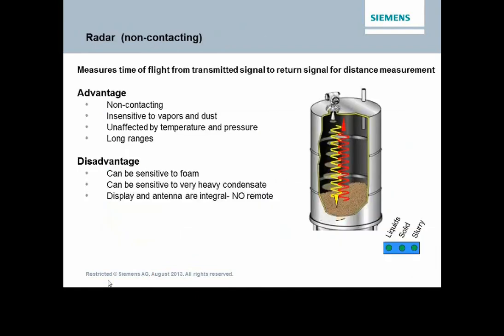When it comes to radar, what's good about it is it's non-contacting. So I don't have to contact the fluid or the solids that happen to be in the tank. So there are definitely some advantages to that. One is that they're insensitive to vapors and dust. Also, we can handle fairly high temperatures and pressures, and these are used in solids industries with ranges all the way to 328 feet. So very long ranges, very quick response. On the negative side, we have sensitivity to foam. There can be problems with heavy condensate. And when it comes to radar, we don't have the option of going with remote. So it's going to be direct. I can always take that output and go to a separate display, but the general unit itself does not go into remote applications.